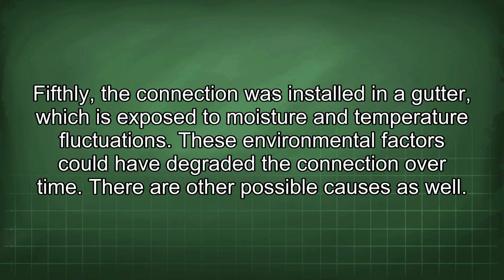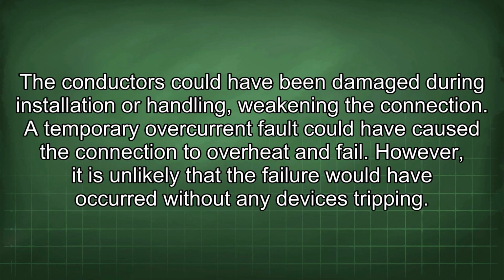Fifthly, the connection was installed in a gutter, which is exposed to moisture and temperature fluctuations. These environmental factors could have degraded the connection over time. There are other possible causes as well. The conductors could have been damaged during installation or handling, weakening the connection. A temporary overcurrent fault could have caused the connection to overheat and fail. However, it is unlikely that the failure would have occurred without any devices tripping.